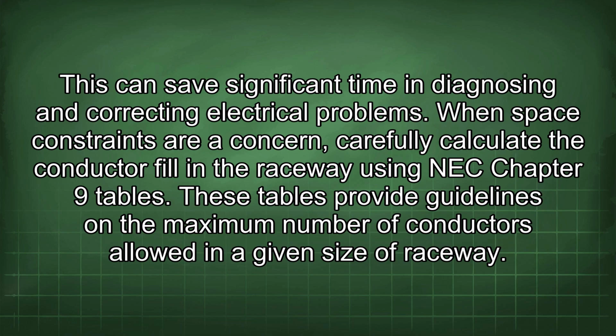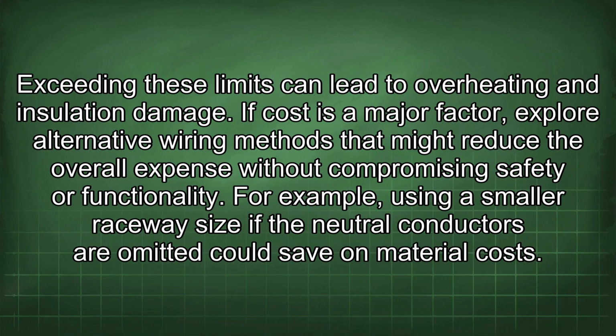When space constraints are a concern, carefully calculate the conductor fill in the raceway using NEC Chapter 9 tables. These tables provide guidelines on the maximum number of conductors allowed in a given size of raceway. Exceeding these limits can lead to overheating and insulation damage.